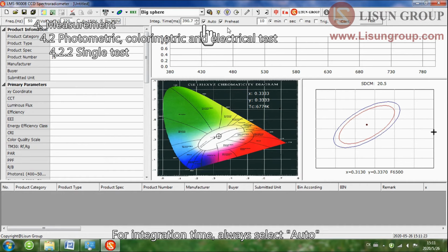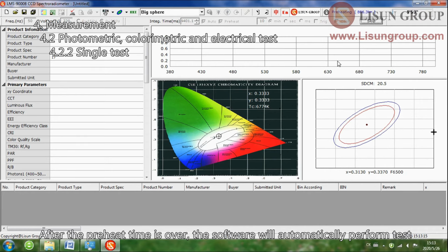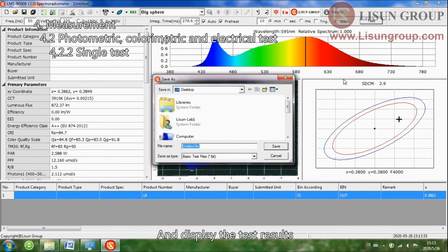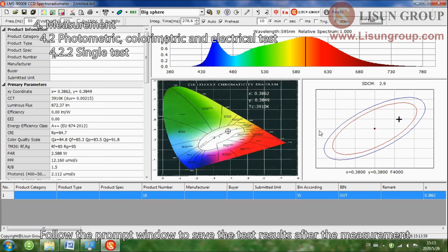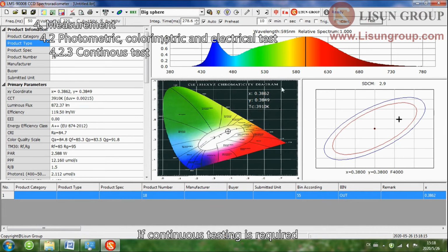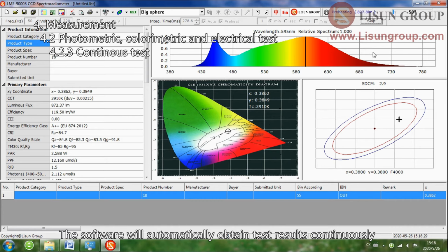For integration time, always select auto, enter a reasonable preheat time, and click test to start the test. After the preheat time is over, the software will automatically perform the test and display the test results. Follow the prompt window to save the test results after the measurement. If continuous testing is required, enter the appropriate preheat time and check continuous testing. Click test. The software will automatically obtain test results continuously with the preheat time as the interval.